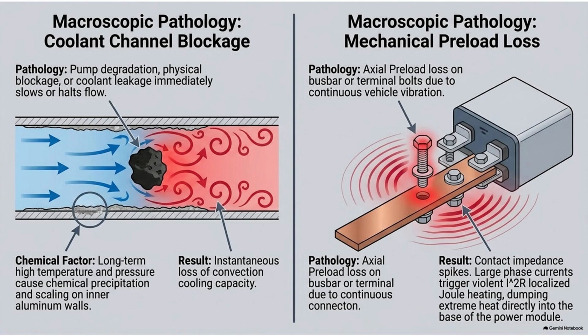The entire heat transfer system relies on forced convection pushing cold liquid past hot metal to carry the thermal energy away. Right. If you lose that fluid flow because a pump seizes up, the convective cooling drops to zero almost instantly. The heat has nowhere to go. But looking at the engineering protocols, it isn't just about a physical blockage, like a piece of debris getting stuck in a pipe. The really insidious problem they highlight is chemical scaling on the aluminum walls.